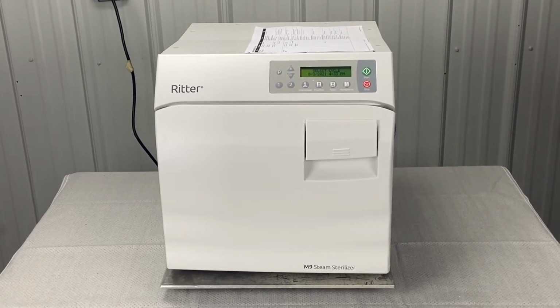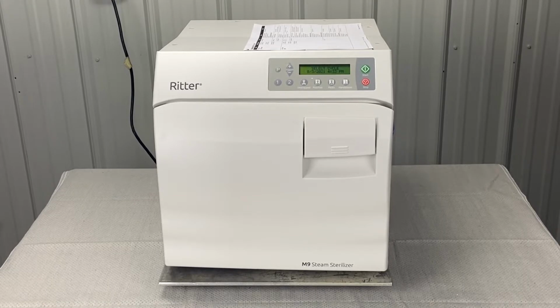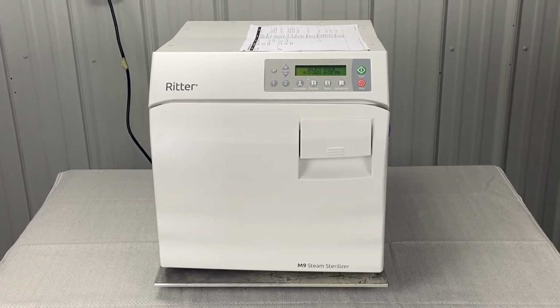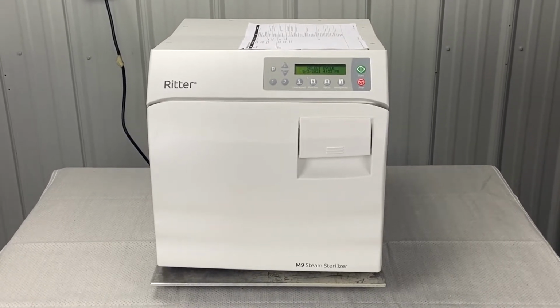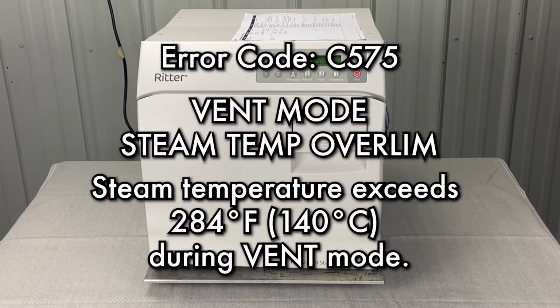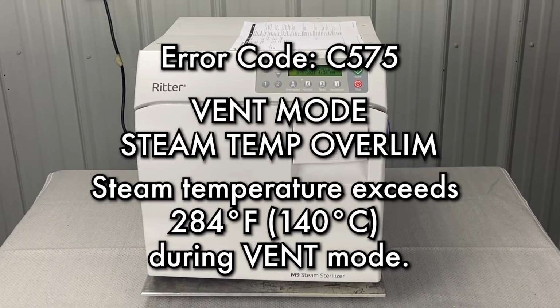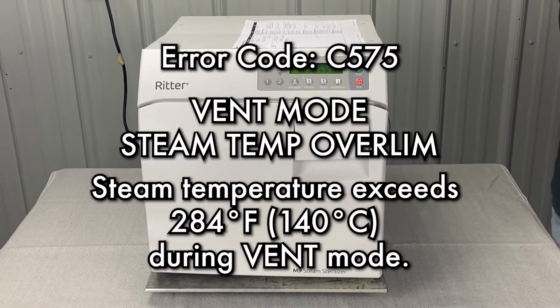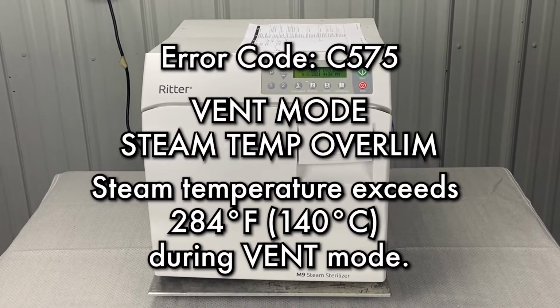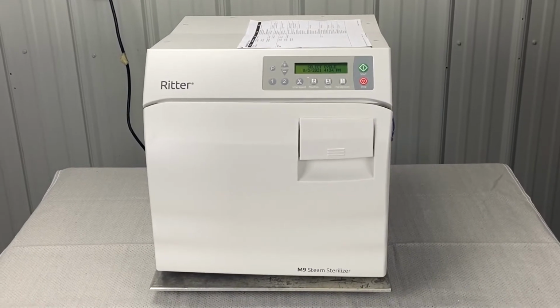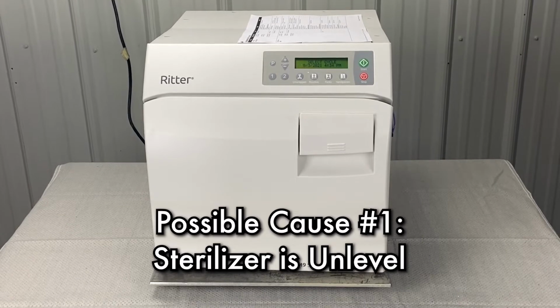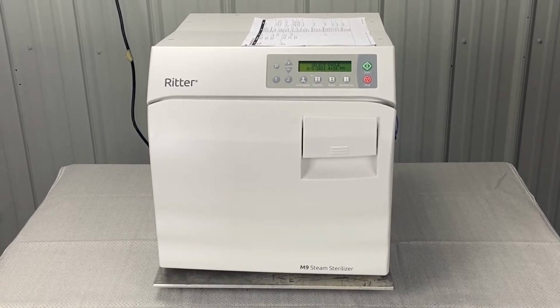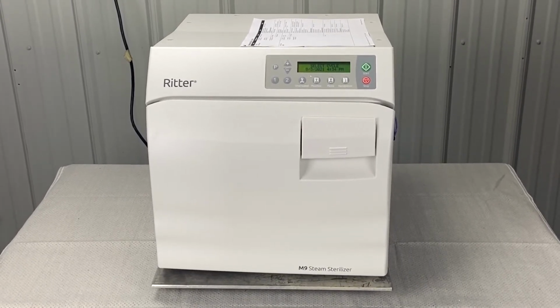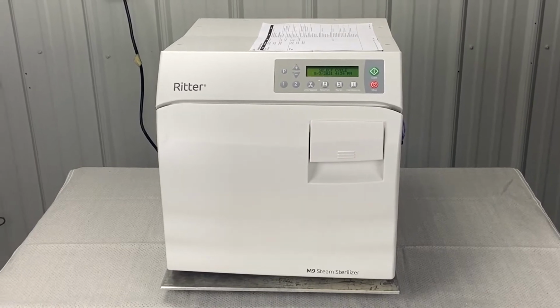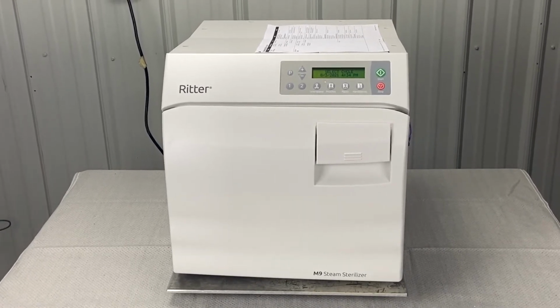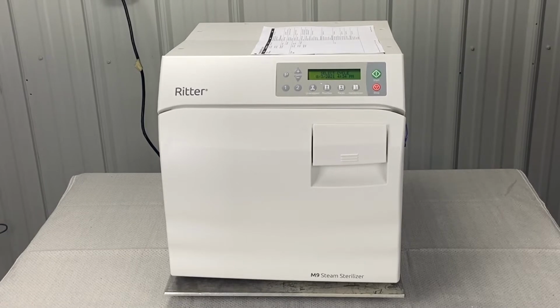So right now we will go over error code C575. Vent mode, steam temp over limit. Steam temperature exceeds 284 during vent mode. The sterilizer being unlevel is a possible cause. Verify the support surface is level. Verify water on all sides of the chamber is equal. The action is to place the sterilizer on a level support surface.